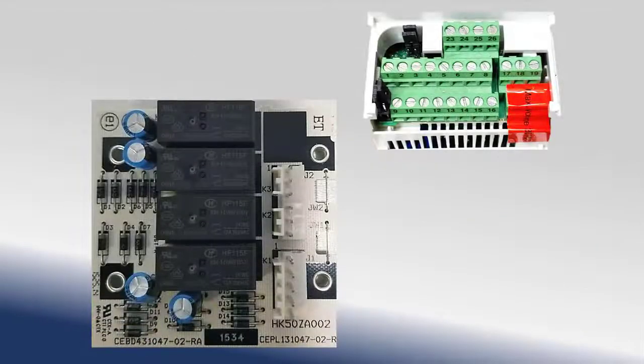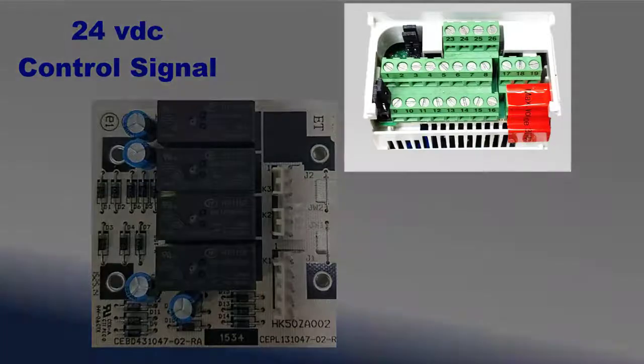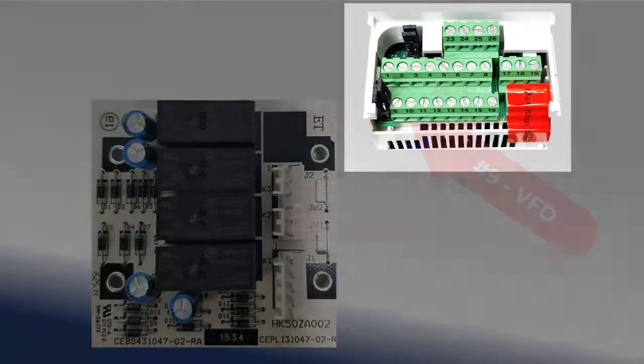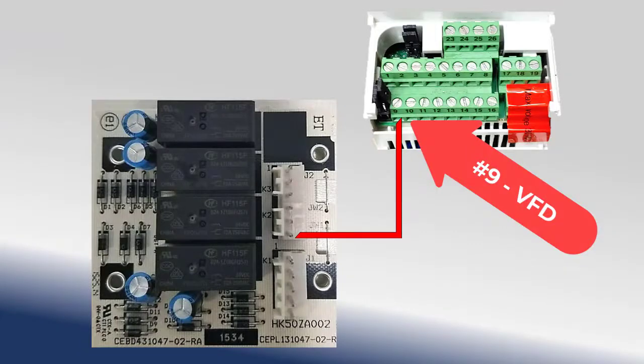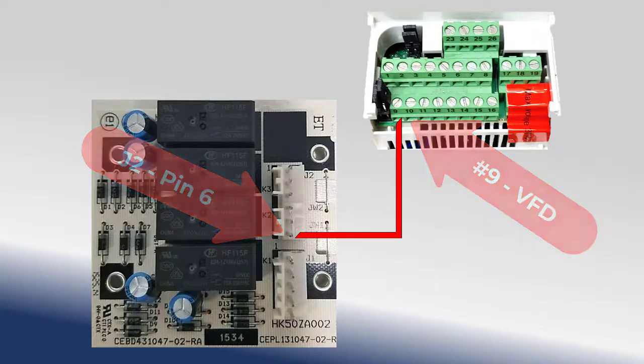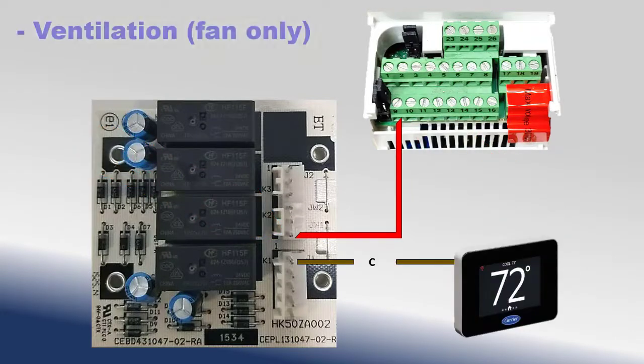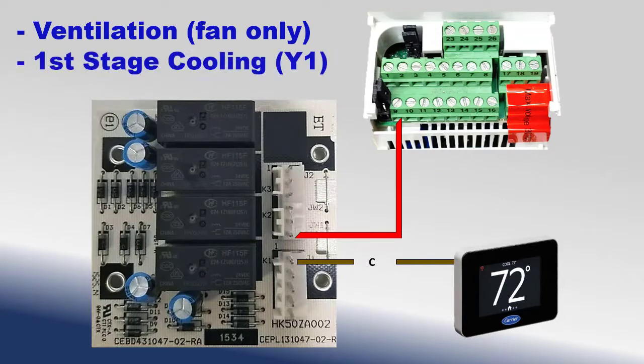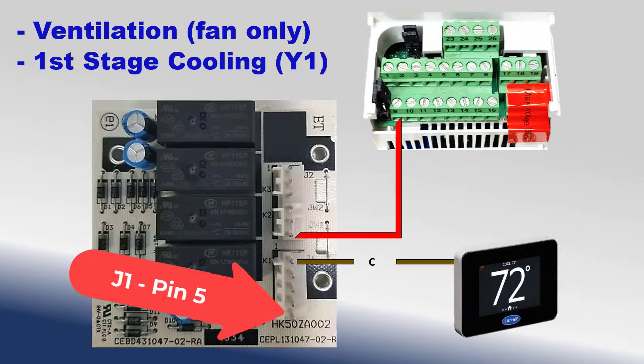This 24-volt DC control voltage is generated by the VFD and routed from terminal number 9 on the ACS320 VFD terminal strip to the fan control board terminal J2, pin 6. During ventilation operation, or the first stage of cooling in two-stage equipment, the thermostat's G signal is routed to the fan speed board at terminal plug J1, pin 5.